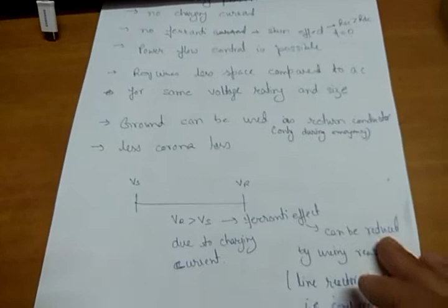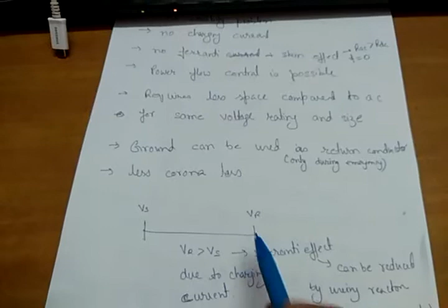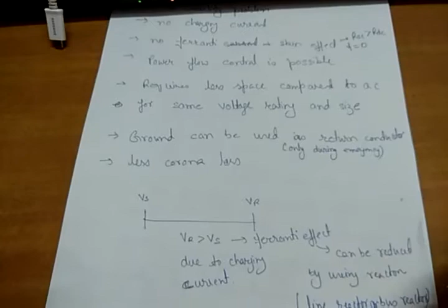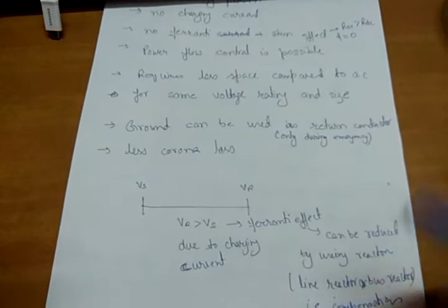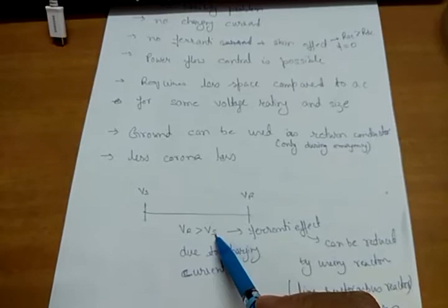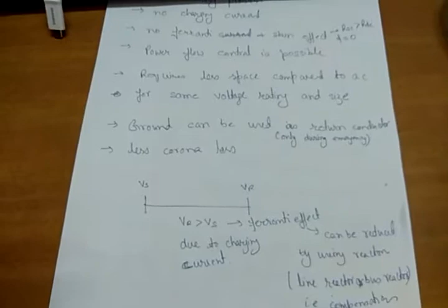No Ferranti effect means, I will show it here. This is my sending end voltage. This is my receiving end. Because of the charging current, because of the capacitance, some current will flow through the capacitor. This Ferranti effect takes place only in case of a lightly loaded system, and the reason for this is the capacitance that is formed between the conductor and ground. So in case of a DC, there is no capacitance, so there will be no charging current, and no Ferranti effect. Whereas in case of AC, due to charging current, the receiving end voltage becomes higher than the sending end voltage, and as the line length increases, the Ferranti effect becomes more predominant.